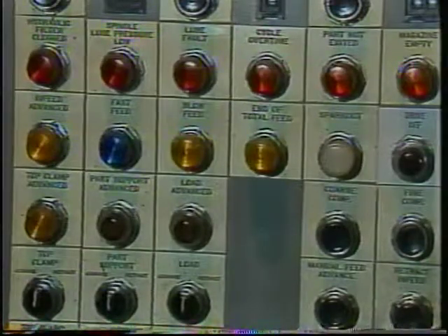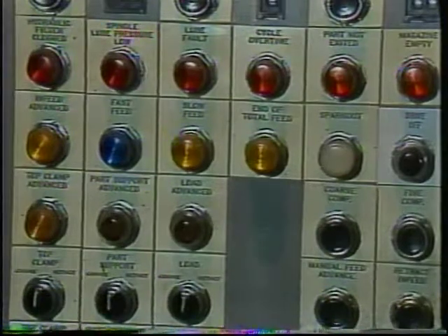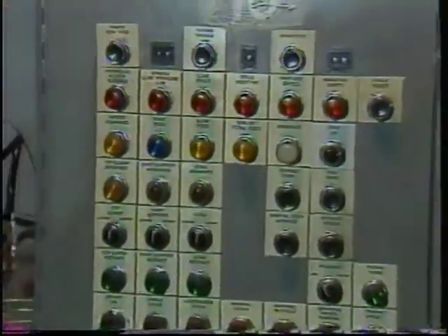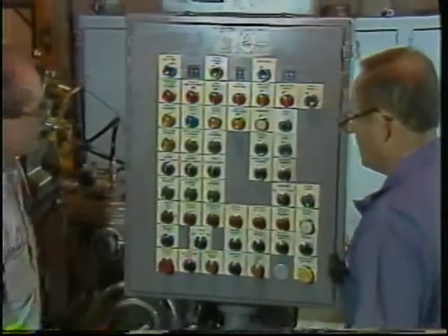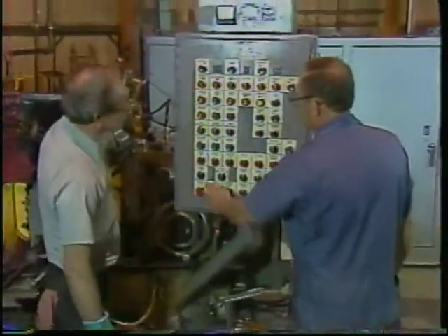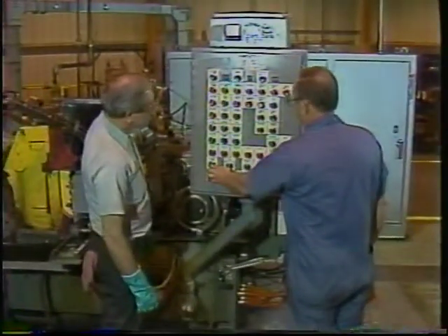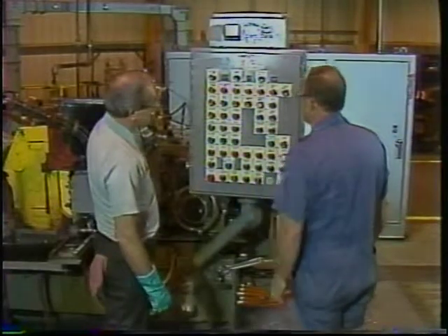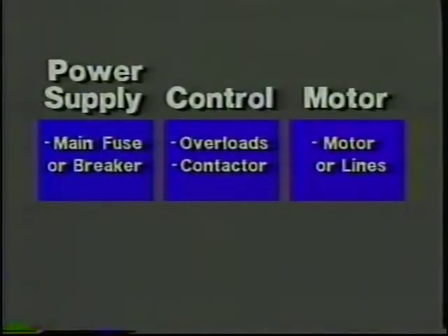Now let's suppose the problem was not an open in the motor, but a dead short to ground in the motor. How would the troubleshooting method lead you to it? Again, the basic symptom would be the same. The motor would not run. And your probable causes and tests would also be the same. You would still start by checking the overloads.